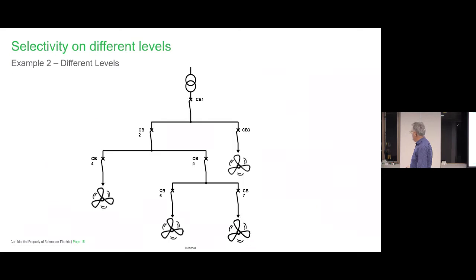But this is with a bigger network. And what's good about that is that the final distribution breaker opens, but all of these are all good. But I can quite honestly say to you, if it was a normal breaker here, and this one had earth leakage up here, we might find that this goes out, then everything goes out. So I'm just going to reinforce, don't put earth leakage in the main breaker, please. We've been asked a number of times lately, and I'm just saying it's just a no.